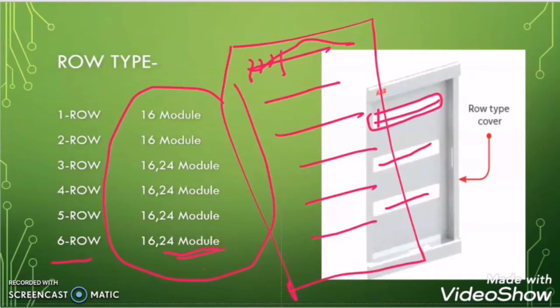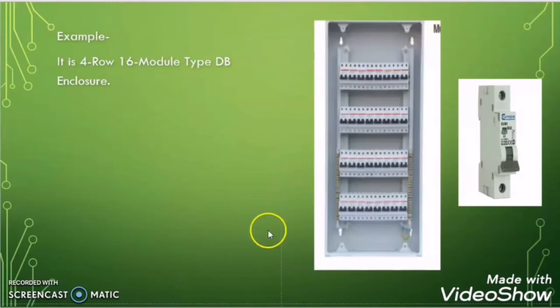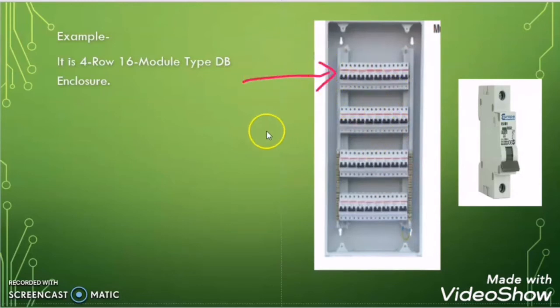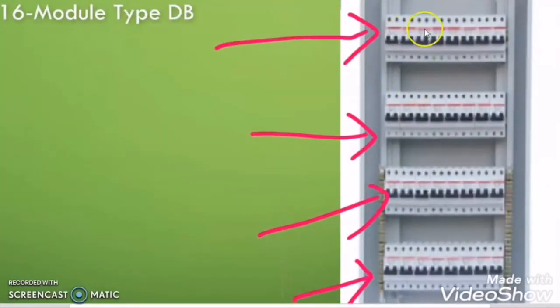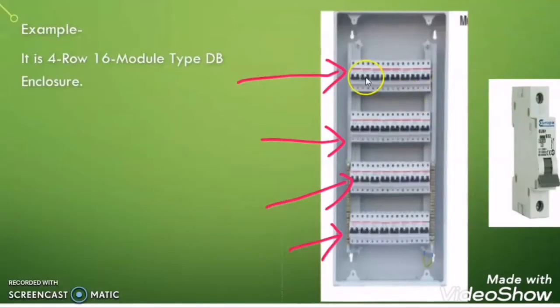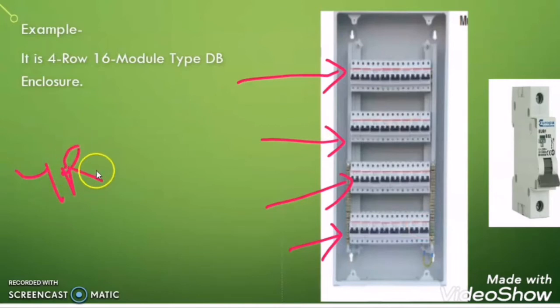Let us take an example. If anyone asks which type of DB enclosure it is, you can say it is a four row enclosure because there are four rows. Then you have to count the breakers in each row — counting gives 16 modules per row. So this is a four row 16 module panel.